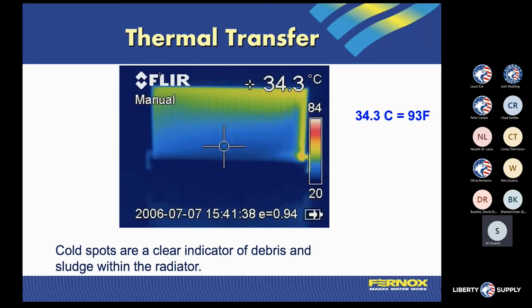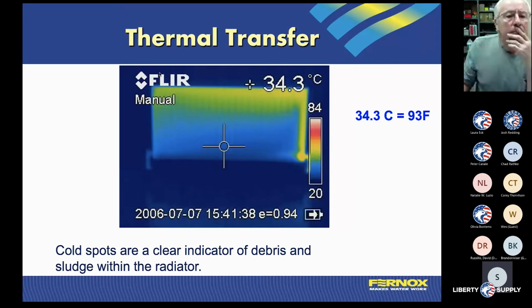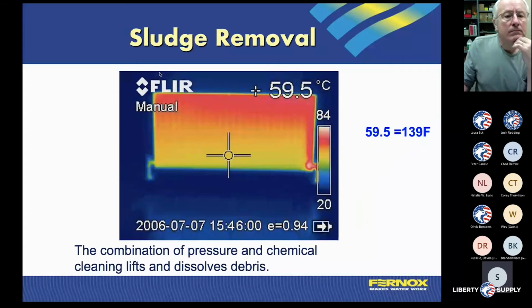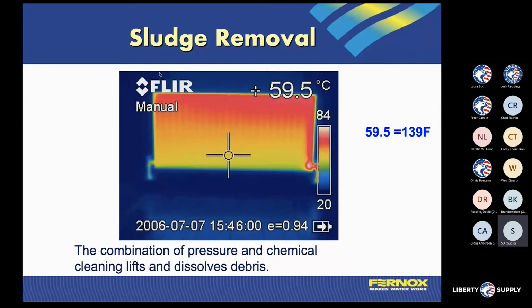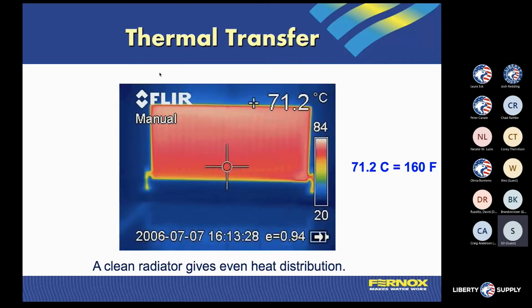So in this same particular application, the radiators were fouled up as well as the heat exchanger that we just talked about. Before cleaning, the best temperature we could get out of it was 93 degrees. After we flushed and cleaned it that first go around, we got it up to 139 degrees of discharge temperature. That's an amazing amount of difference in discharge temperature, and that's going to relate to your cycle time. Then, after flushing it again, we get to a place where we get up to full temperature.